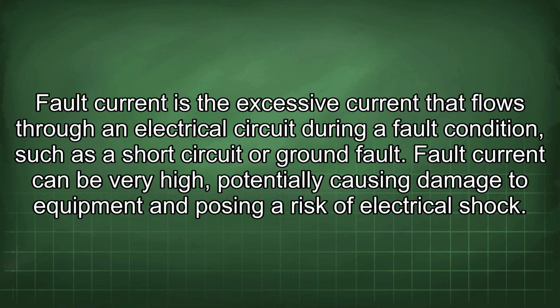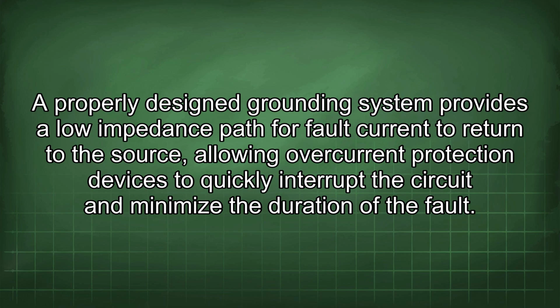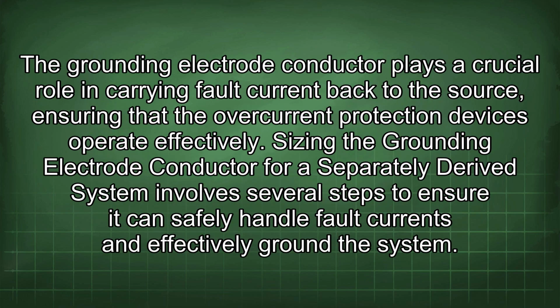Fault current is the excessive current that flows through an electrical circuit during a fault condition such as a short circuit or ground fault. Fault current can be very high, potentially causing damage to equipment and posing a risk of electrical shock. A properly designed grounding system provides a low impedance path for fault current to return to the source, allowing overcurrent protection devices to quickly interrupt the circuit and minimize the duration of the fault.